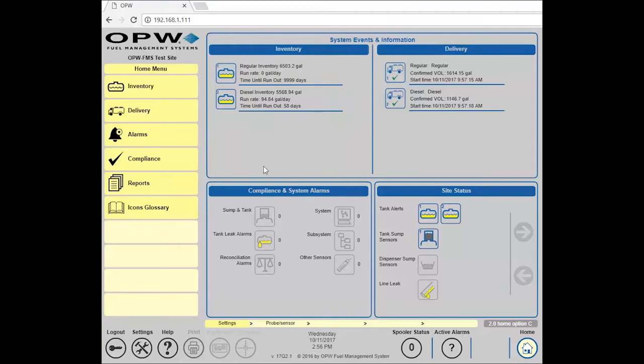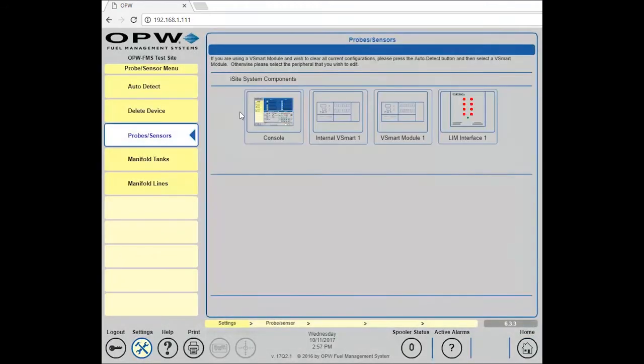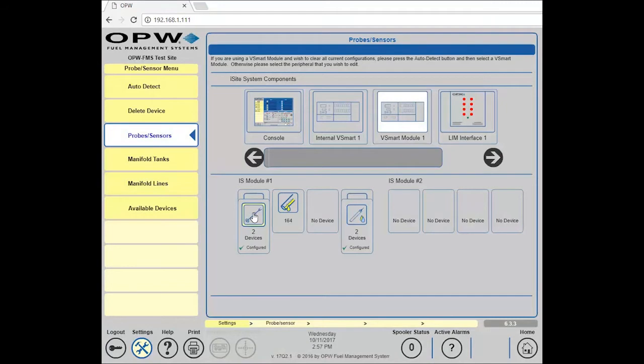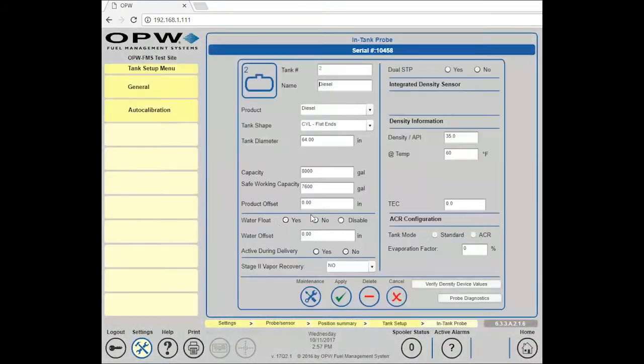But first let's look at what a probe looks like with just a normal water float installed on it. We've logged onto this system as an administrator or a technician, and we would click Settings, Probes and Sensors, Probes and Sensors. Select our vSmart that has the probes installed. And if we just look at one that does not have the AEF installed, we see that we have an area down here asking for our water float settings, whether we want to use the water float or not. And up here in the top right-hand corner, it asks us about an integrated density sensor, which we don't have either, so there are no fields there to populate.